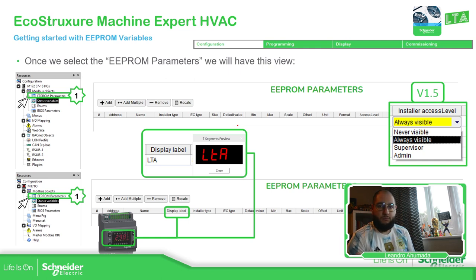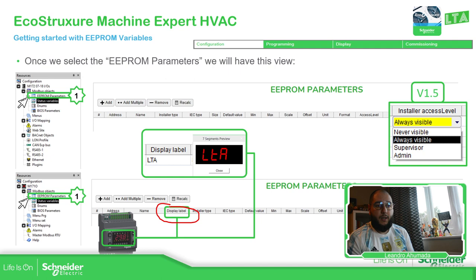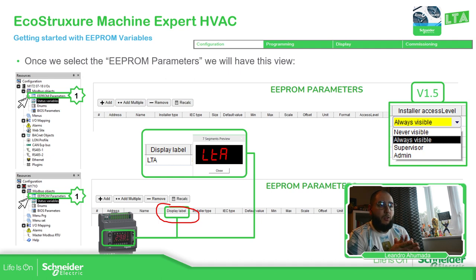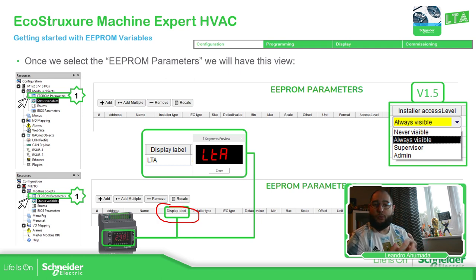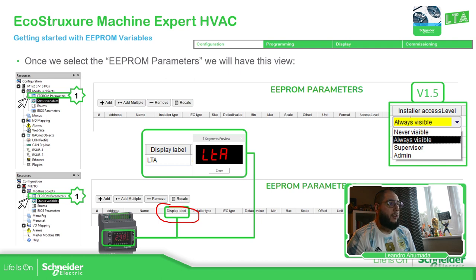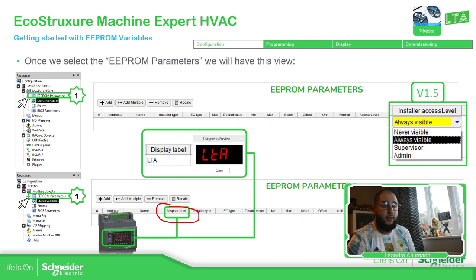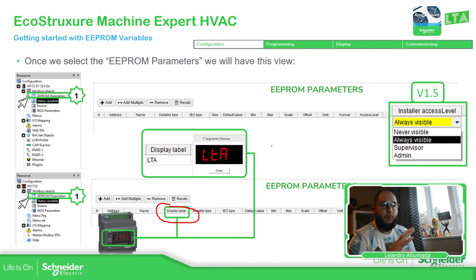We have a similar view to the status values. For the Modicon M171 Optimize, there is an additional column for display label, since that controller has an embedded seven-segment display — so we need to put some characters here to visualize the variable. Something new is the installer access level, which I'll cover in a separate video because it deserves its own explanation. Essentially, this is the same but uses a different area of memory.